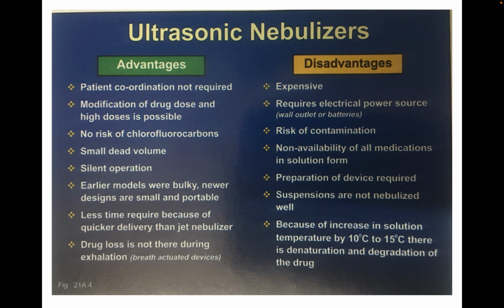Not all medications are available in solution form, preparation of the device is required, and suspensions are not nebulized well. Because the solution temperature increases by 10 to 15 degrees, there is denaturation and degradation of the drug. So these are some of the advantages and disadvantages of the ultrasonic nebulizer.